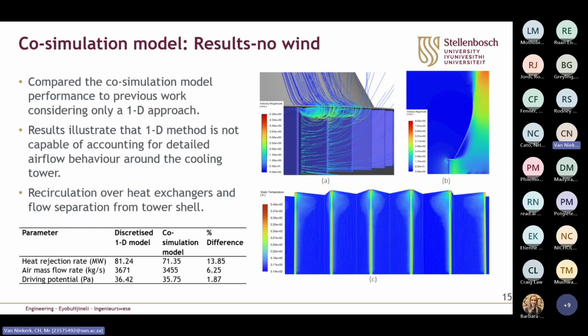And these discrepancies are a result of the 1D model not being able to capture some of the complex flow effects that we see in the CFD. For example, if we look at the top figure, we see this large recirculation vortex forming in front of the heat exchanger tube banks, which effectively reduces the amount of air mass flow rate that can flow through the heat exchangers. And this reduction in air mass flow rate causes a reduction in heat transfer rate. And this vortex also causes an increase in overall air inlet temperature across the heat exchanger tube banks, which we can see with this maldistribution of air temperature across the front of the heat exchangers in the same area as where this vortex is, which further reduces the overall heat transfer.